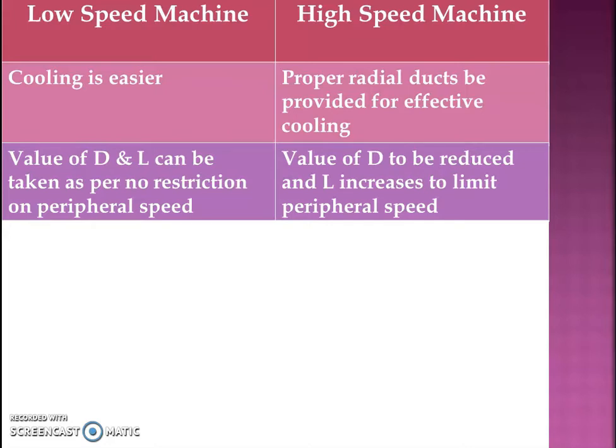Then, regarding peripheral speed: in a low speed machine, there is no special restriction on peripheral speed, so the values of d and l can be chosen as needed. While in a high speed machine, peripheral speed is very important and must be limited within a permissible value. Therefore, the diameter d must be reduced and the length l should be increased to limit the peripheral speed.